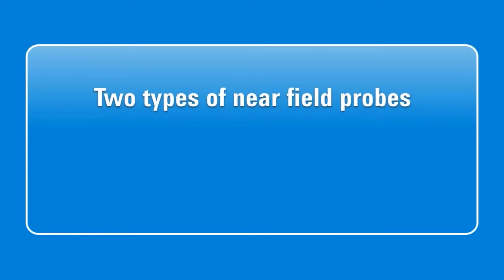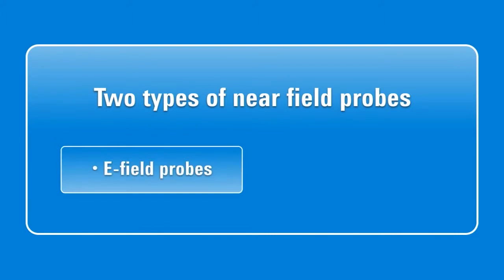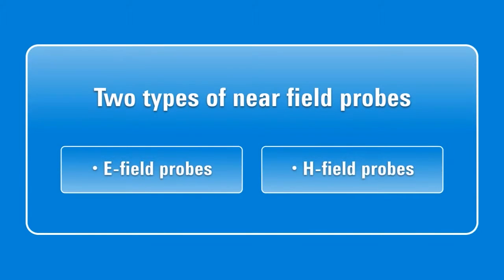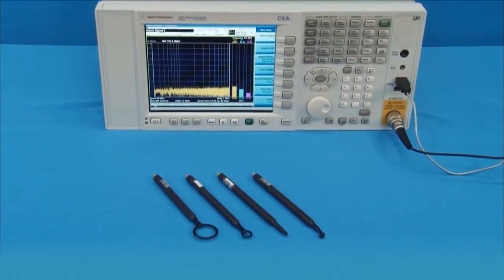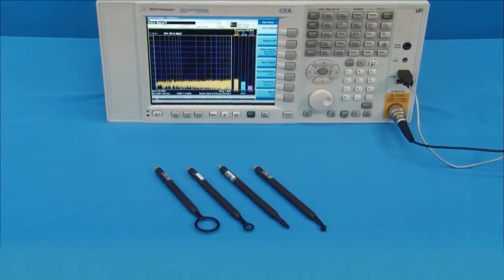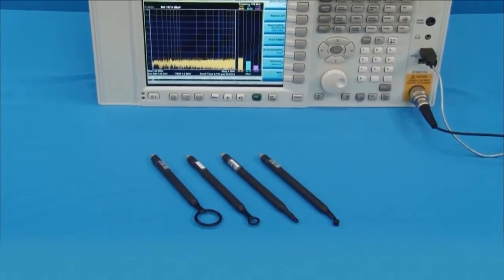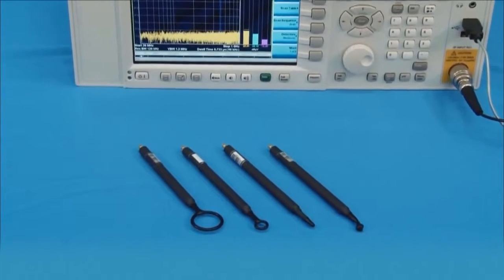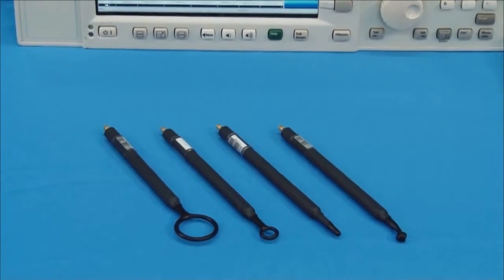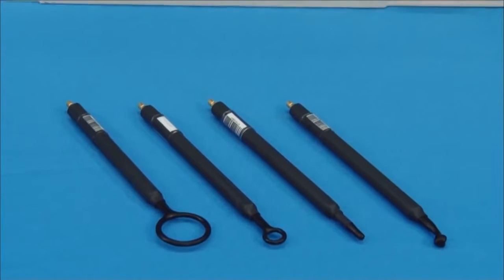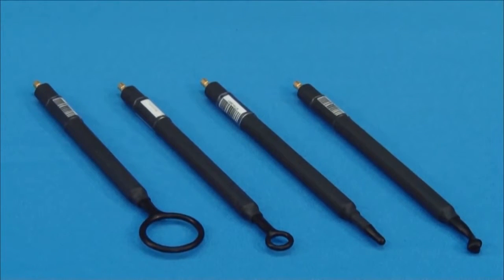There are two types of near-field probes. One is E-field probes which detect electric field. The other is H-field probes which detect magnetic field from emission sources. H-field probes are more commonly used to locate emission sources in near-field tests because the H-field fades faster than the E-field as the distance increases. In other words, H-field probes provide better resolution.